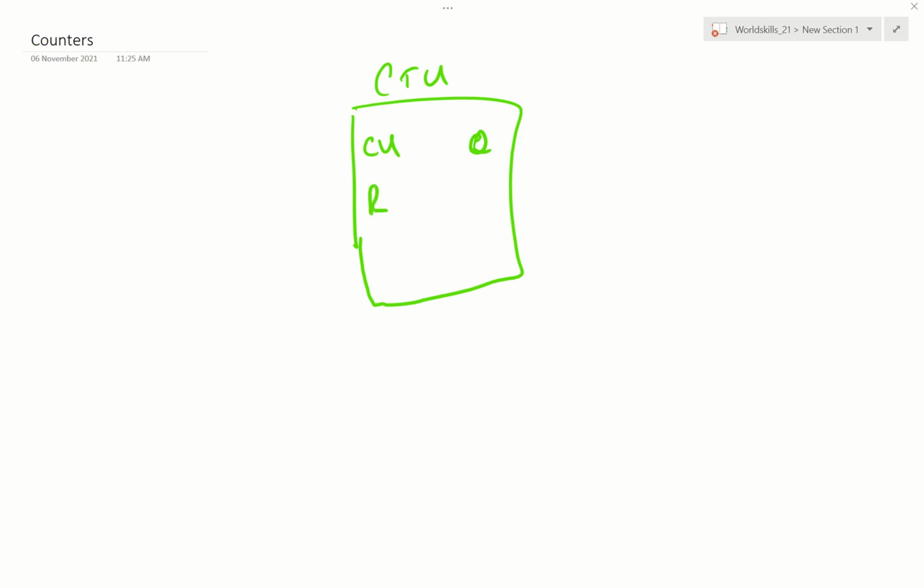If we quickly try to refresh our memory on what the counter block looks like, we use a CTU, and it's got a CU, or input, that we're going to count. We have a Q, the output, when we've reached a count. We have the reset, which is important, and then we have the PV and the CV. The PV just sets the value of our counter. The CV is the value of the counter at any moment in time. We don't usually use it with HMI screens and things like that.